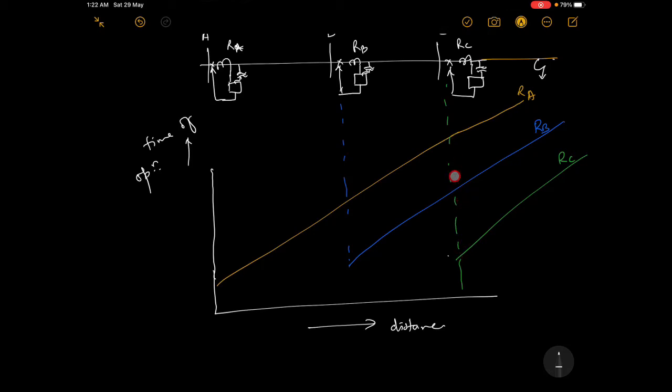So inherently we are trying to implement this delay. This is what we call backup protection. So this is our primary protection for this fault, then this will become our backup protection. If there is a fault here, which relay will operate? Obviously this, correct? If there is a fault here, RB relay will operate, and if this fails to operate due to some maloperation in this relay, then after some time lapse, this will certainly protect it. So this is backup protection, and this is what we want.